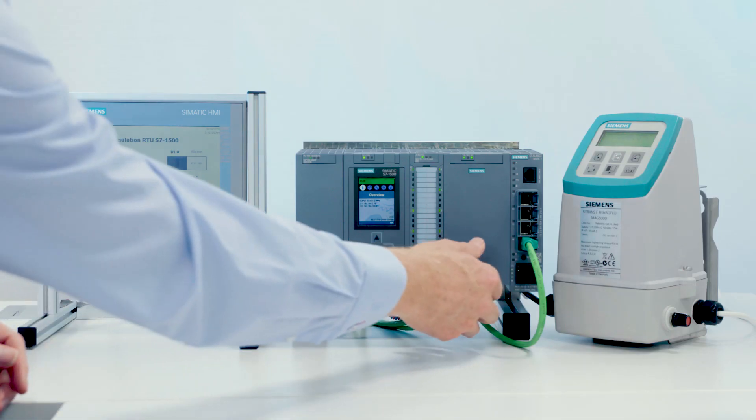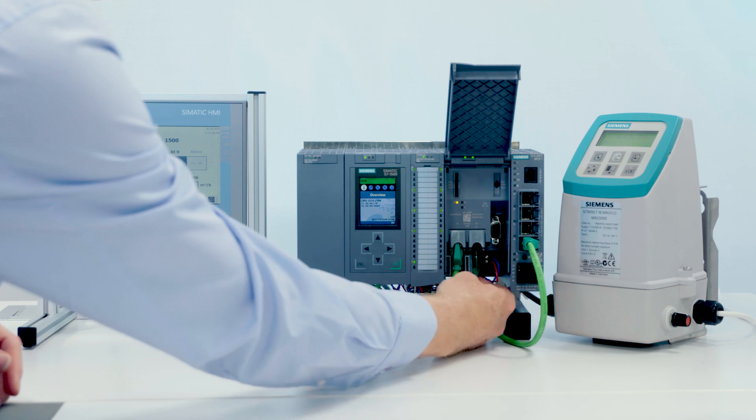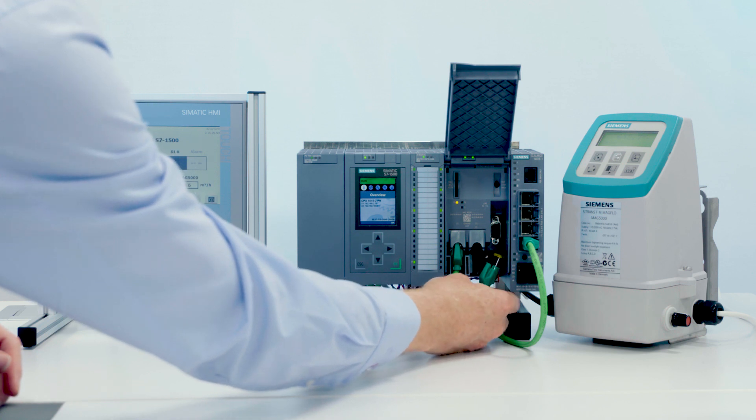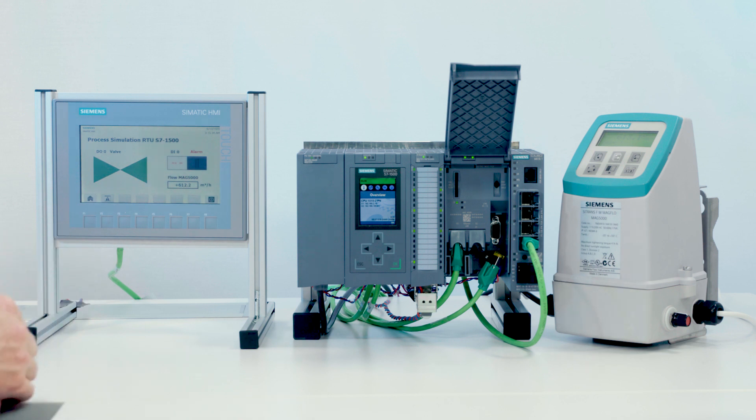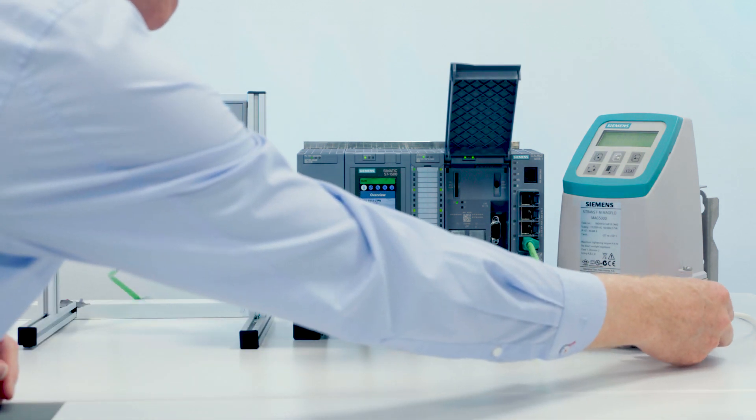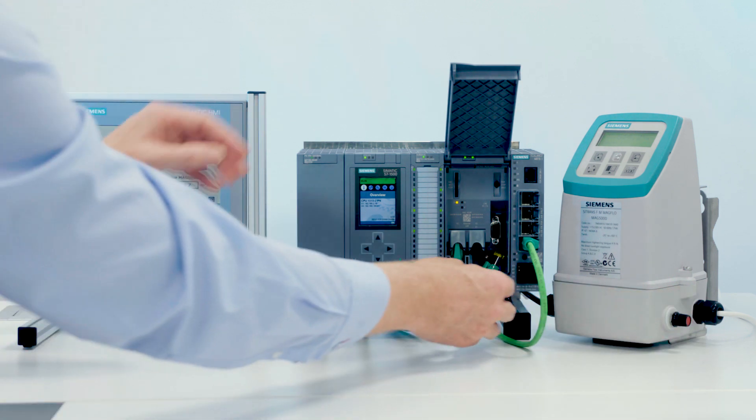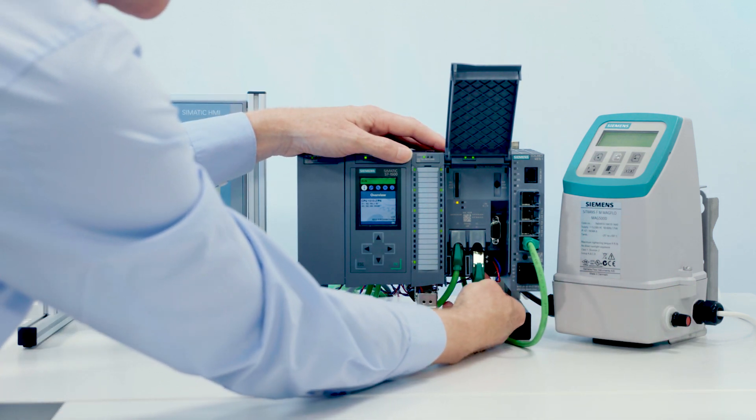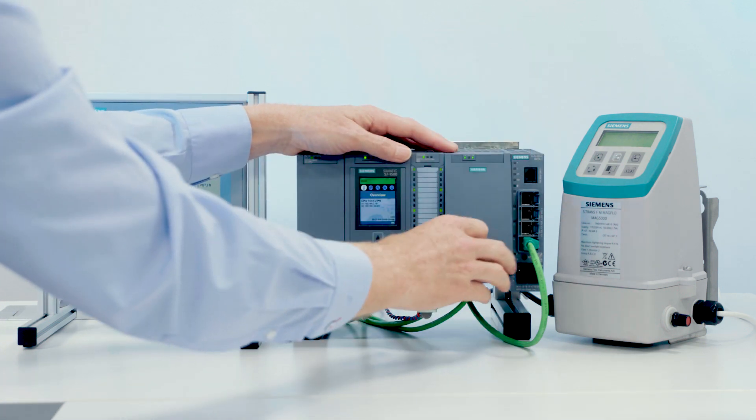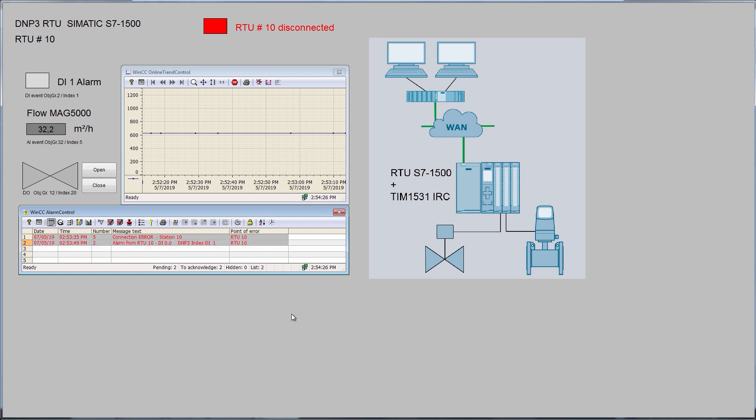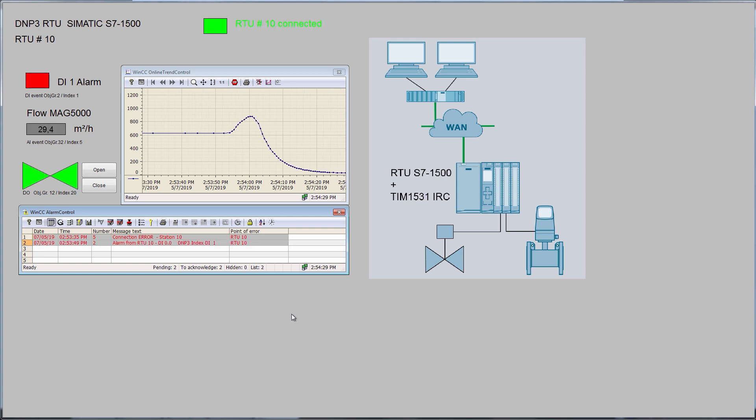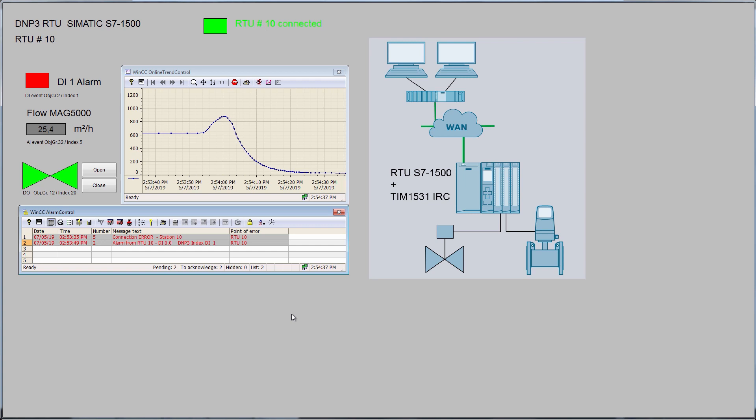If the connection from the RTU to the control center should be interrupted, the process data is buffered on the RTU with a timestamp. When the connection is re-established, the process data is transmitted and archived in chronological order. Now I will interrupt the connection. I am generating an alarm and changing the flow. Now I will restore the connection. As soon as the connection is active again, the RTU transmits the buffered data. In the message list, we see the alarm that occurred during the connection interruption. In the measured value archive, we see a complete measured value curve, including the values that were recorded in the RTU during the interruption.